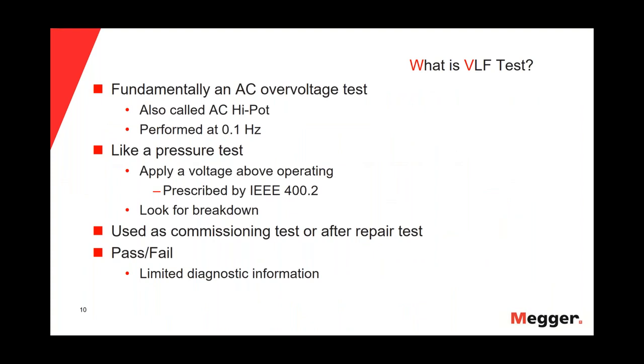What is the VLF test? Let's start talking about the VLF test. The VLF test is fundamentally an AC over voltage test. It's also called AC Hi-Pot. And the frequency we use for this AC over voltage test is 0.1 hertz.